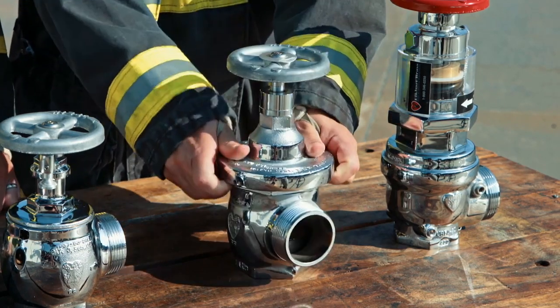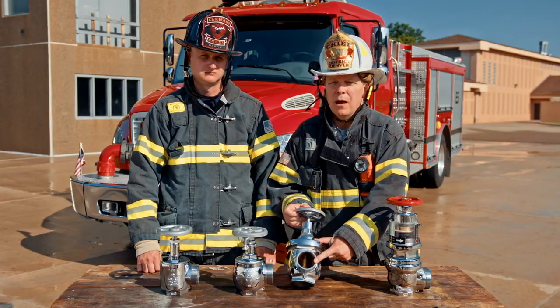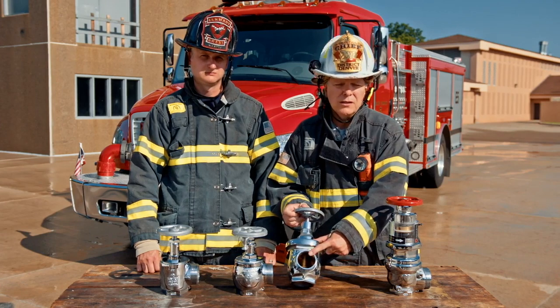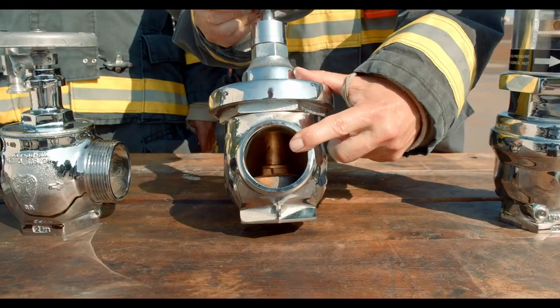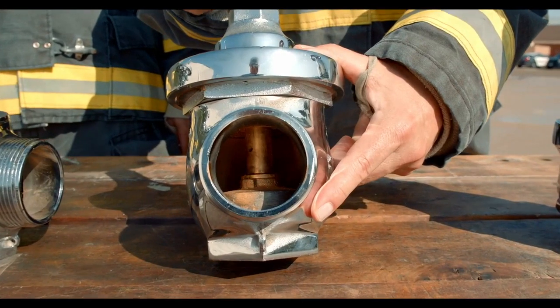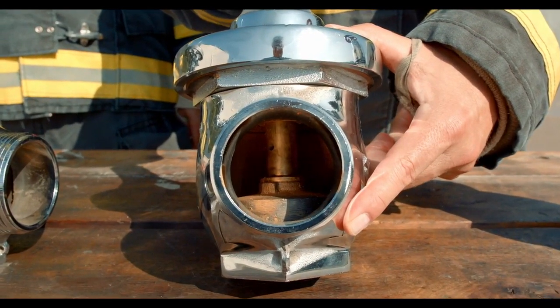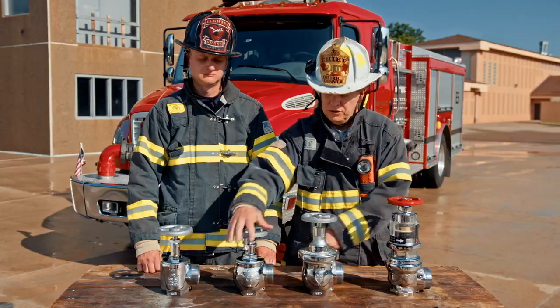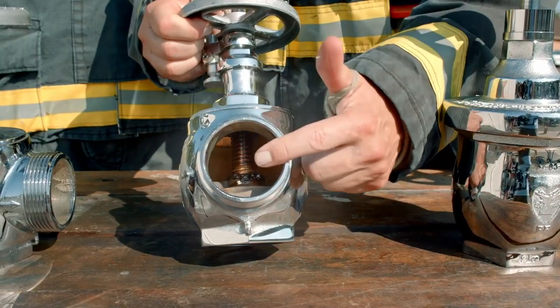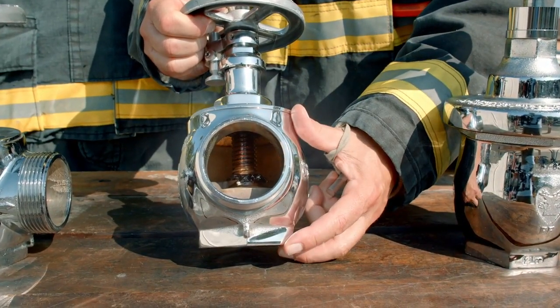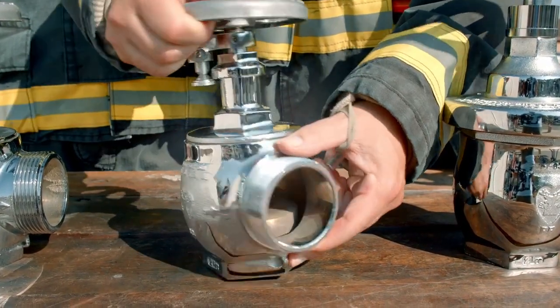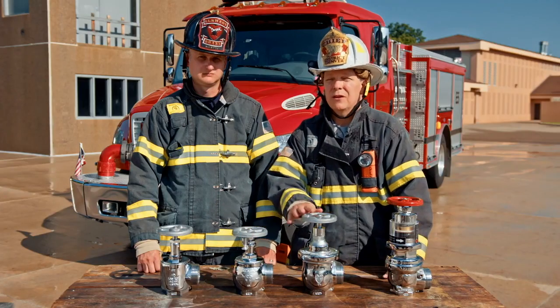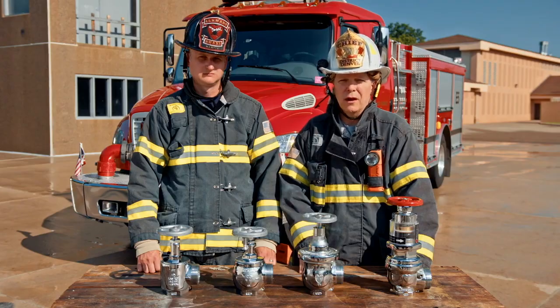It's also important to note that if firefighters aren't sure, they can take the cap off and look inside the valve. When you see the smooth stem, you have some sort of internal operating pressure reducing valve. It's a smooth stem so that the PRV can float and operate properly, adjusting pressure. Versus on a standard hose valve outlet, you have a threaded stem, indicating that you have a standard valve outlet, but once again, you have to look on the outside to see if there's any external restricting devices.